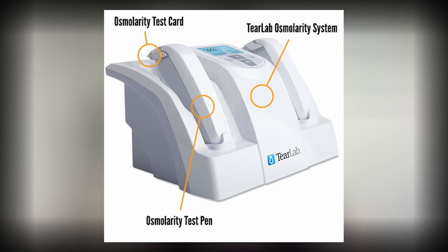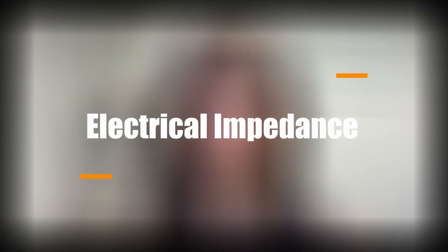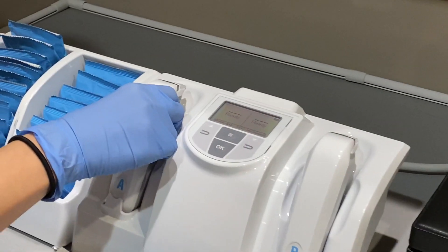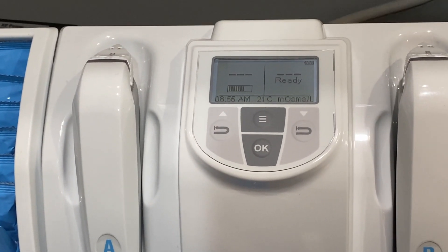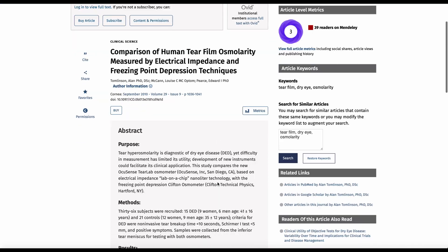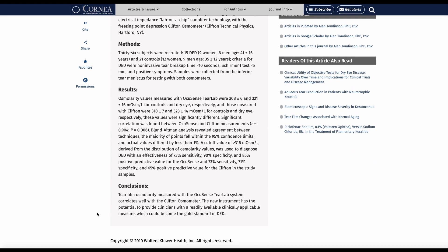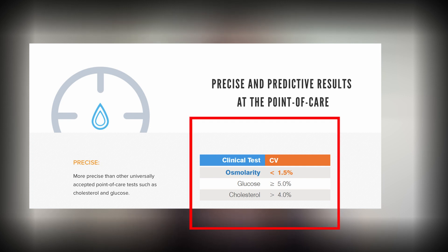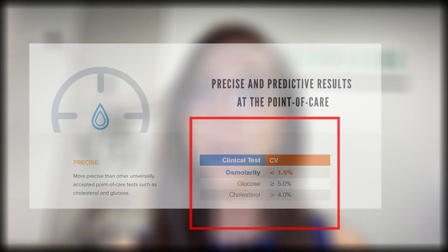The TearLab uses a handheld sampler with a single-use microchip embedded with gold electrodes that measures the electrical impedance of the tear fluid sample in a tiny channel in the chip. To perform the test, the clinician collects a very small sample of tear fluid — the patient is asked to look up and the tip of the device is positioned along the lower lid closest to the ear. The tear meniscus is absorbed by capillary action, and the device is then docked into the reader, which calculates and displays the osmolarity measurement in just a few seconds. A recent paper compared the TearLab Osmometer against the freezing point depression method — the industry gold standard — and determined that the TearLab method correlated well with it.